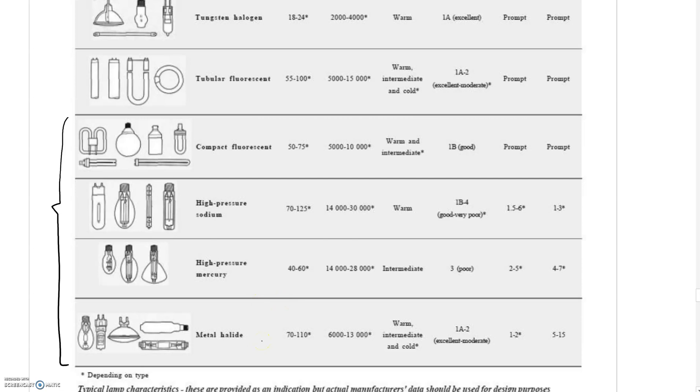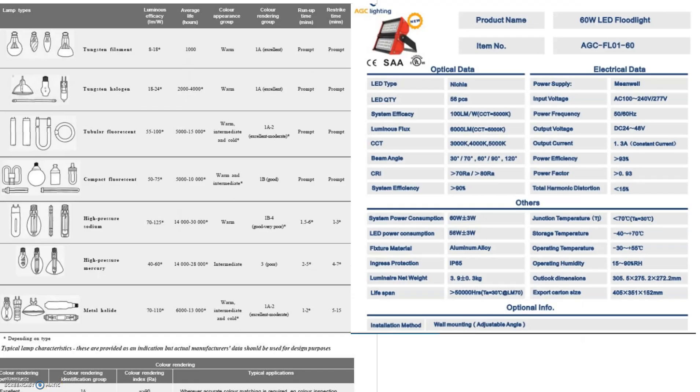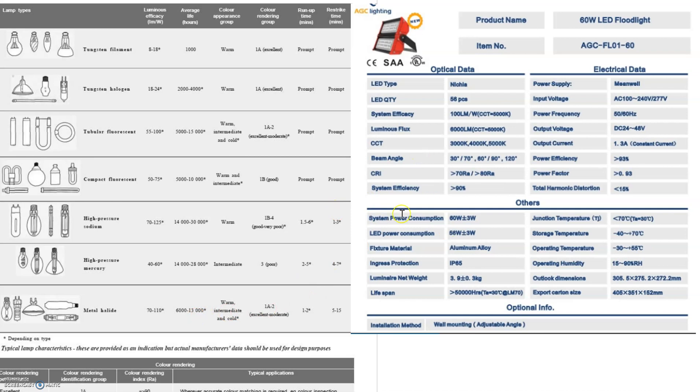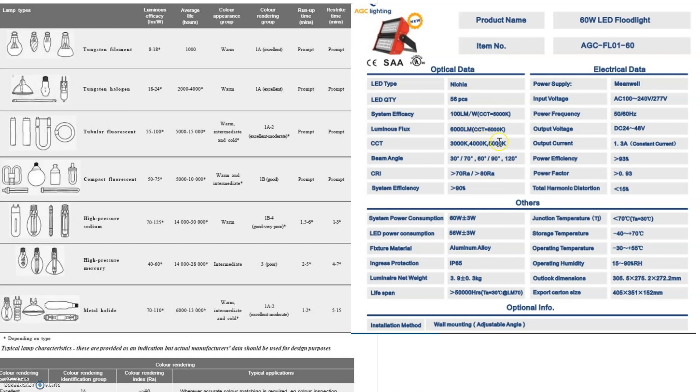In recent times LED lighting has become prominent. Comparing LED lights, if we look at metal halides at 70 to 110 lumens per watt, a similar LED light has an efficacy of 100 lumens per watt with 6000 lumens luminous flux output and very good color rendering.